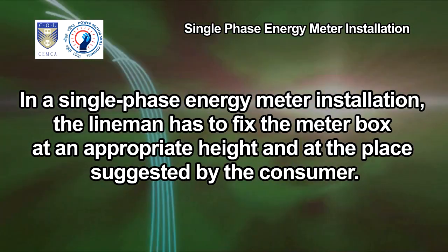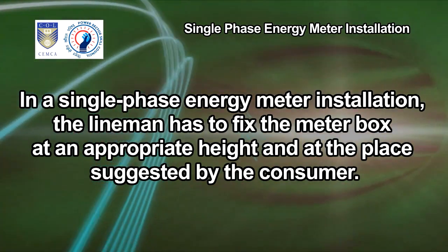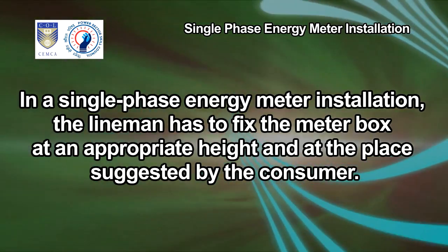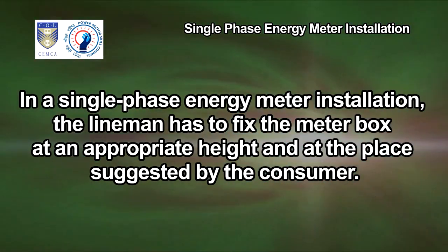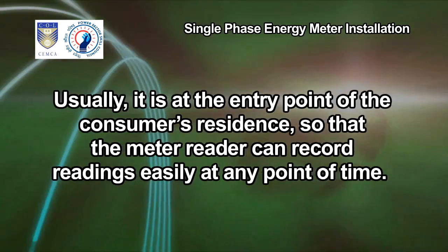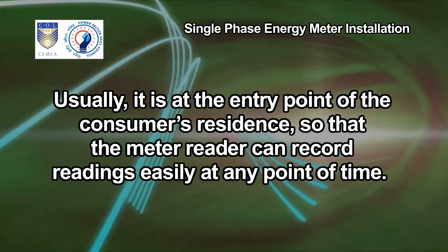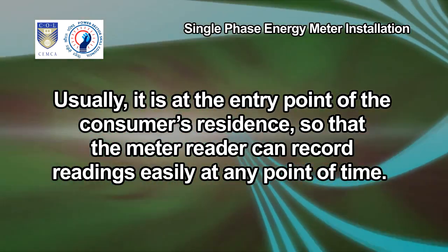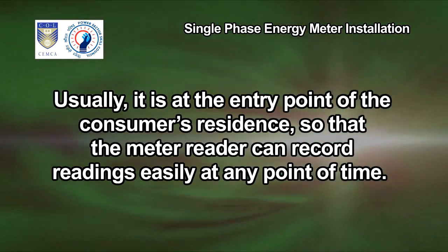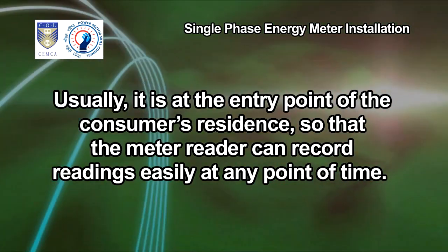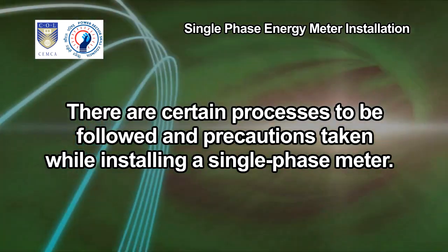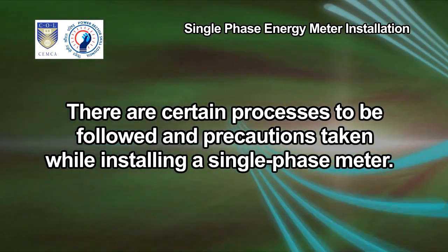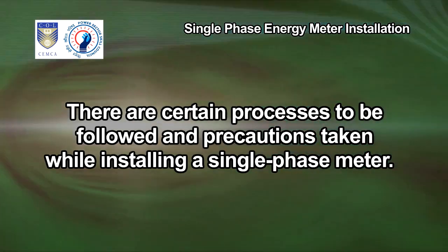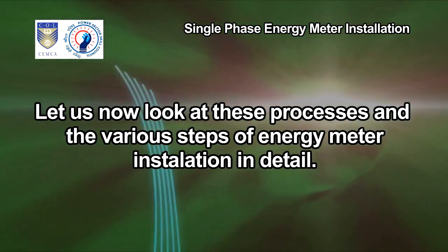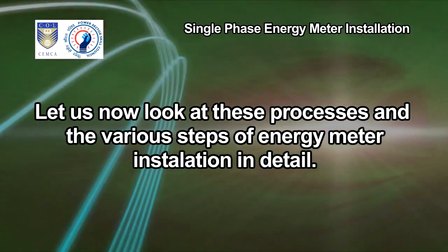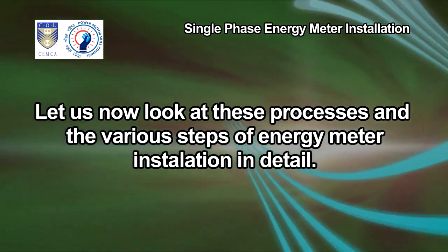In a single-phase energy meter installation, the lineman has to fix the meter box at an appropriate height and at the place suggested by the consumer. Usually, it is at the entry point of the consumer's residence so that the meter reader can record readings easily at any point of time. There are certain processes to be followed and precautions taken while installing a single-phase meter. Let us now look at these processes and the various steps of energy meter installation in detail.